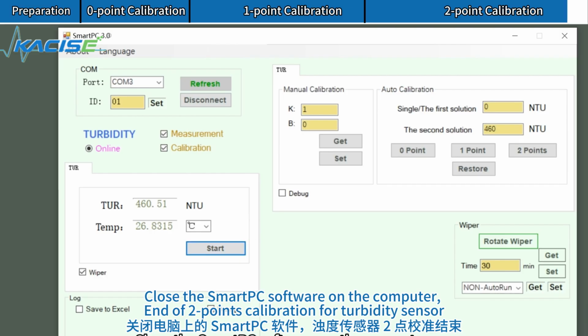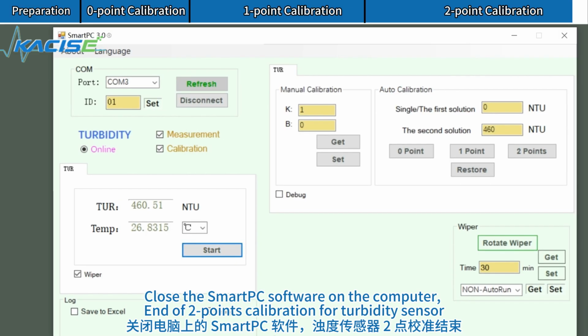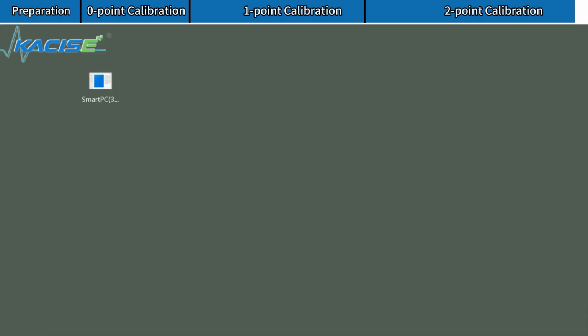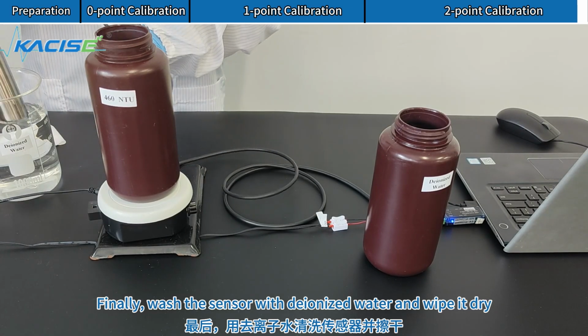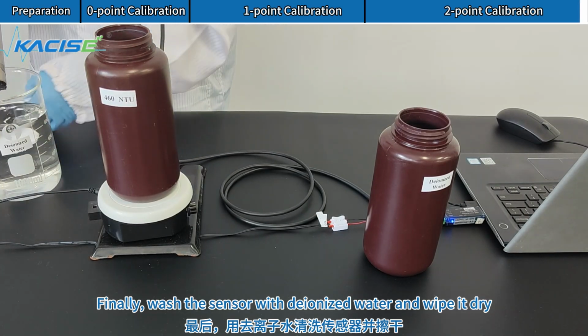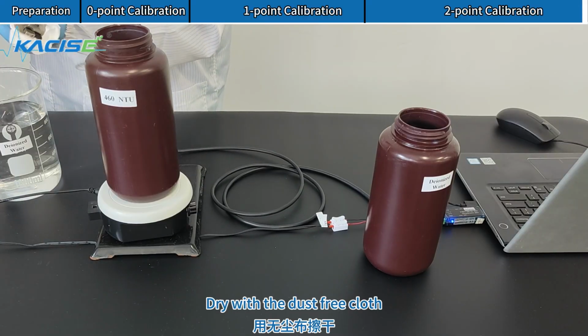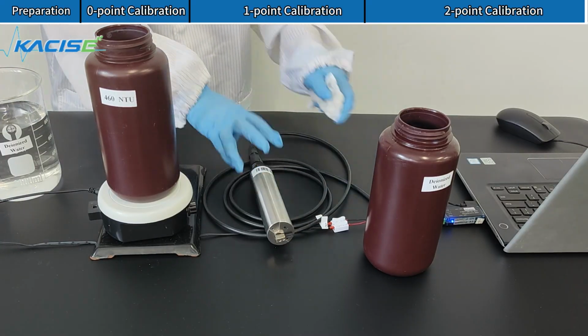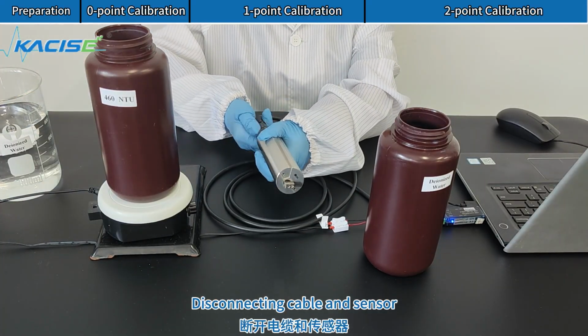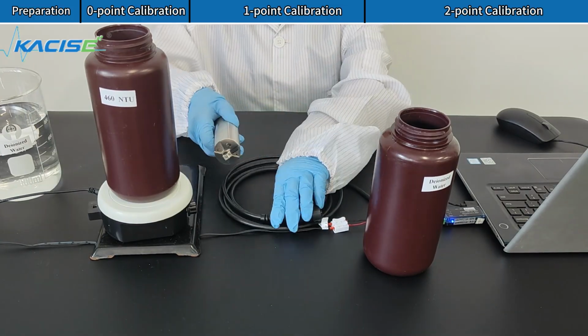Close the Smart PC software on the computer. End of 2 points calibration for turbidity sensor. Finally, wash the sensor with deionized water and wipe it dry. Dry with the dust-free cloth. Disconnecting cable and sensor.